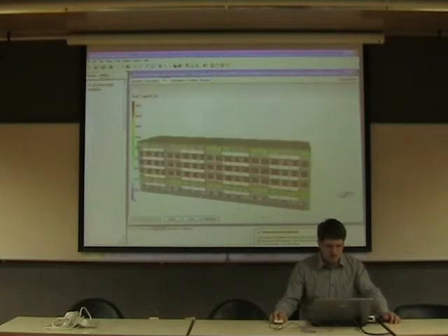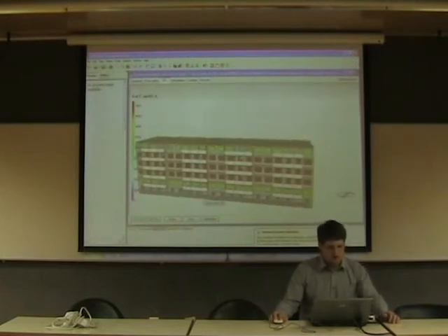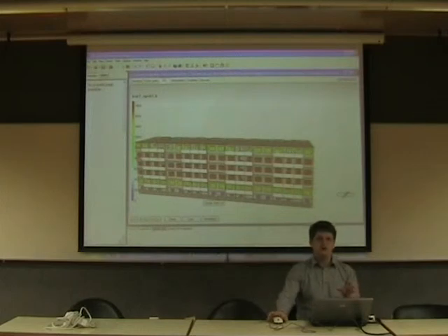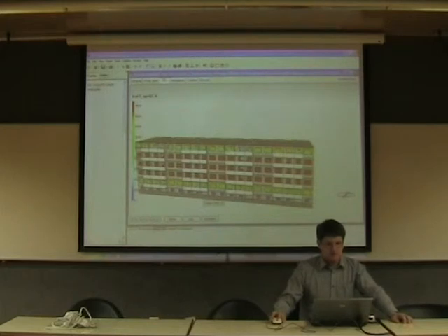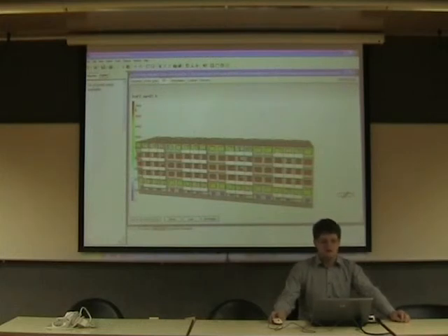This calculation is already made, and here there is no cooling energy. When we don't use cooling energy, this building has big window areas. This is one question: why will the temperature rise above 27 degrees for like 1,800 hours? Because it has big windows.